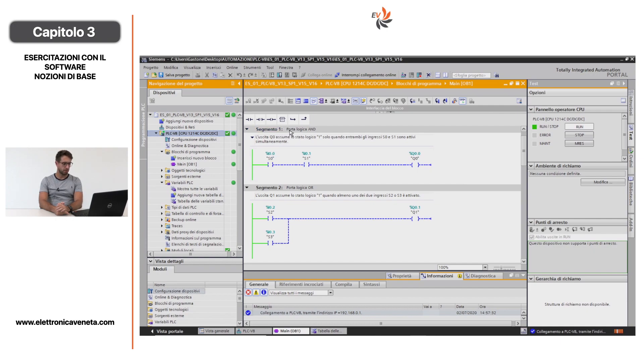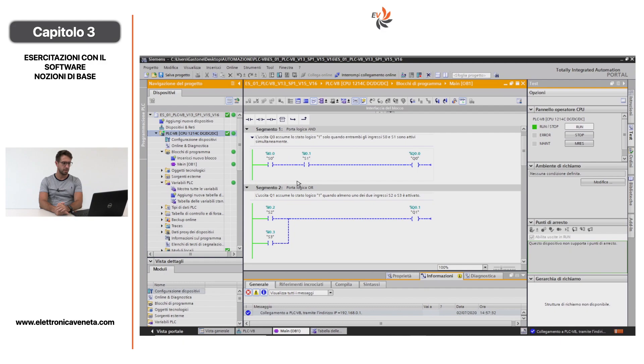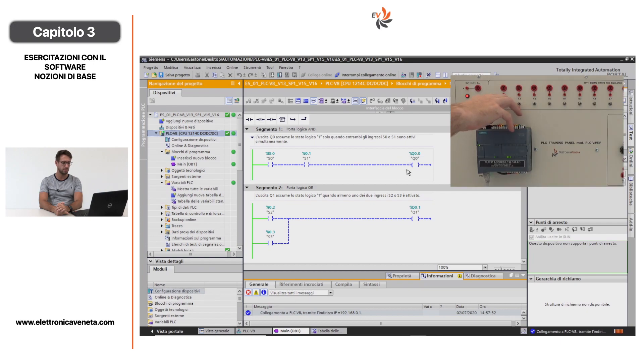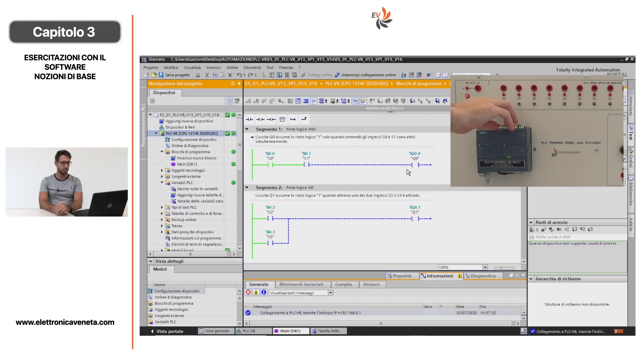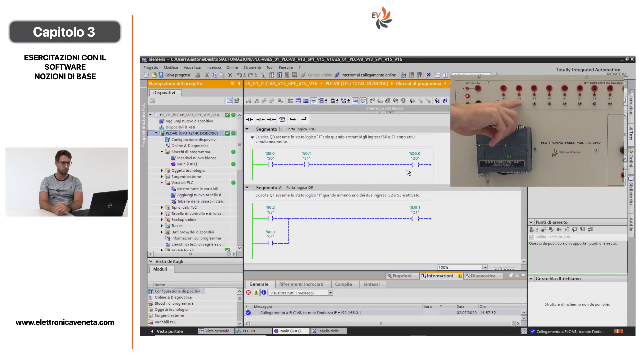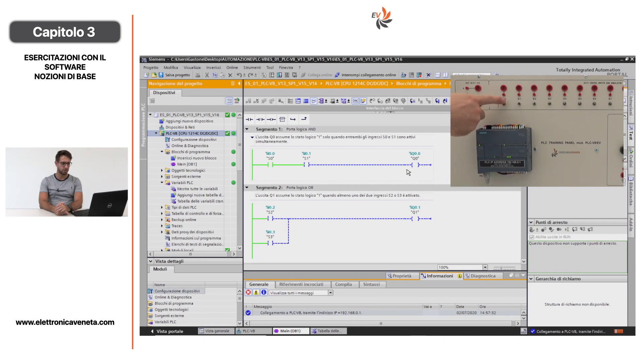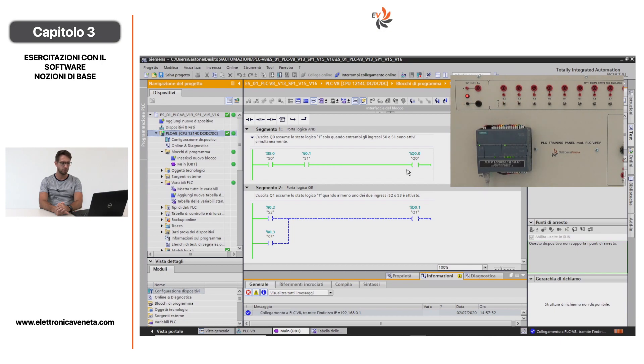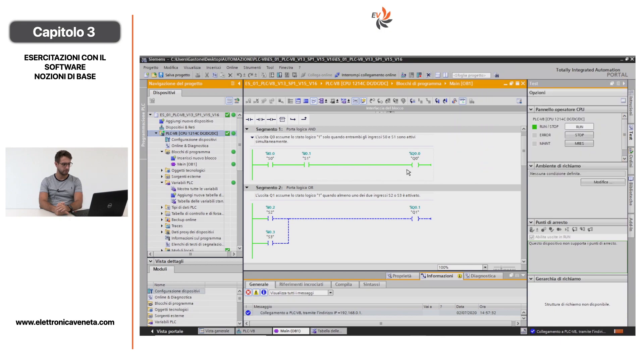Il primo segmento, che corrisponde all'esercizio 1 del manuale, va a descrivermi una logica AND. Quando l'ingresso I0.0 e l'ingresso I0.1 sono allo stato ON, allora mi si abilita l'uscita digitale Q0.0. Andiamo a verificare a pannello. Si vede che con un impulso si illumina l'ingresso I0.0, lo poniamo verso l'alto in modo da mantenere costante lo stato di ON e facciamo lo stesso con l'ingresso I0.1. L'uscita digitale è abilitata, come si vede anche a LED.